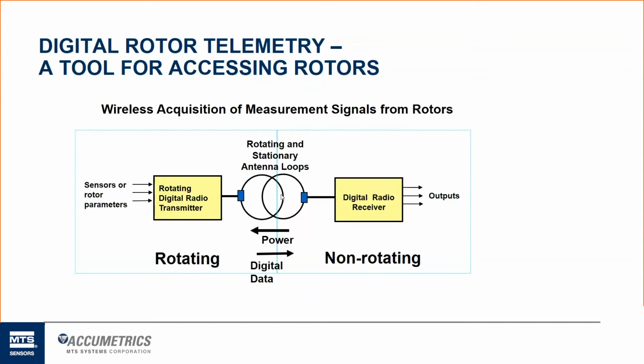So data is flowing this way, and power from induction power, RF radio frequency carrier, is coming across that air gap this way. Once we digitize a signal on the rotor, we send a digital data stream across that air gap. It gets picked up in this loop of wire and then gets run to our stationary digital radio receiver, where we then do some digital to analog conversion and send the end users and power plants those signals. They have some analog 4 to 20 current loop output signals that we provide, and also some Form C contact relays, normally open, normally closed contact relays. And we'll go into that in some more detail in the next few slides. So again, it's the link between the rotating world and the non-rotating world. Power this way, data coming back that way.